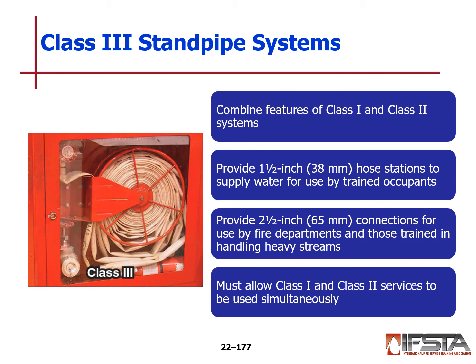Class 3 standpipe systems combine the features of Class 1 and Class 2 systems. These provide 1.5 inch hose stations to supply water for use by trained occupants. They provide a 2.5 inch connection for the use of the fire department and those trained in handling heavy streams. These must allow Class 1 and Class 2 services to be used at the same time. So we'll have a connection, yet the hose station and the hose in the hose station are operable both at the same time.